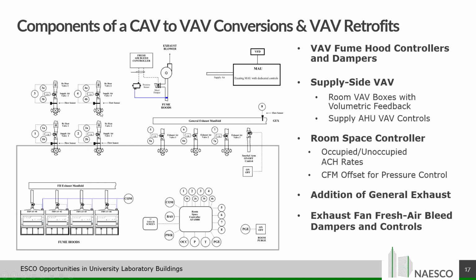Now, it's not just about the exhaust. You have a supply air system coming into the lab as well. So we need to get control of that by controlling the existing valve or adding a new one. You're going to have a reheat actuator you're going to want to control as well. And you're going to want to control this supply to maintain proper lab pressurization. So that's a strategy called CFM offset. So from all of these devices, you need to get volumetric feedback to know what all your exhaust is from this lab. And then this comes into what's called a room space controller. It's the brains of your lab.